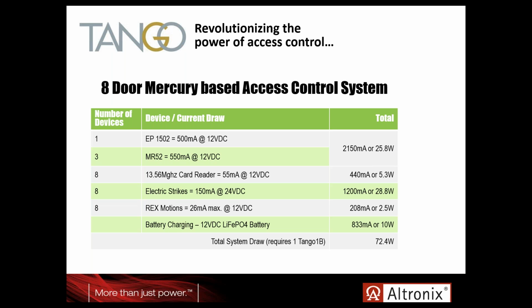When we add in the card readers, max current draw of 55 milliamps, 8 electric strikes at 150 milliamps, or 28.8 watts as shown to the right. Then we throw in our request-to-exit motions or other ancillary devices, which in this case need 2.5 watts.